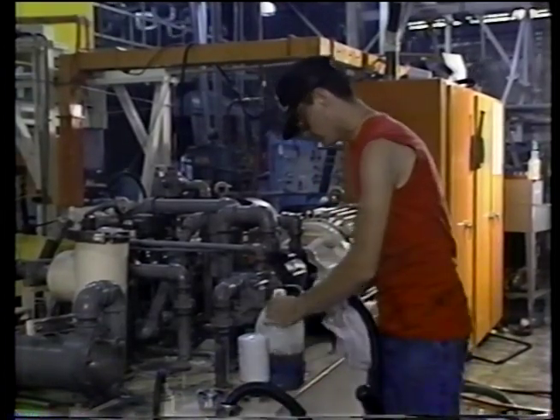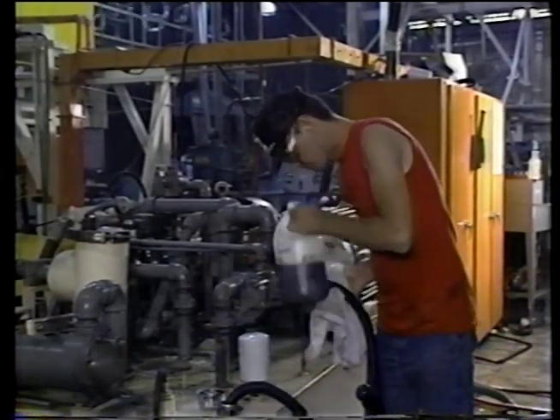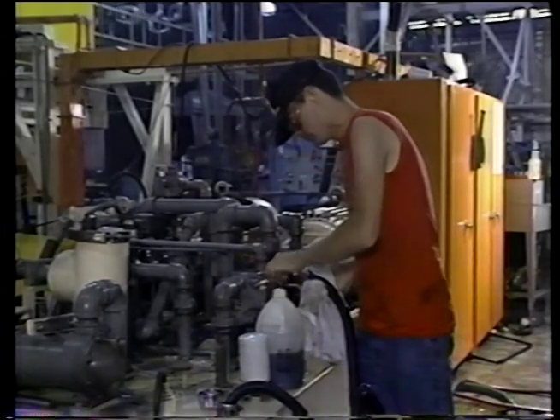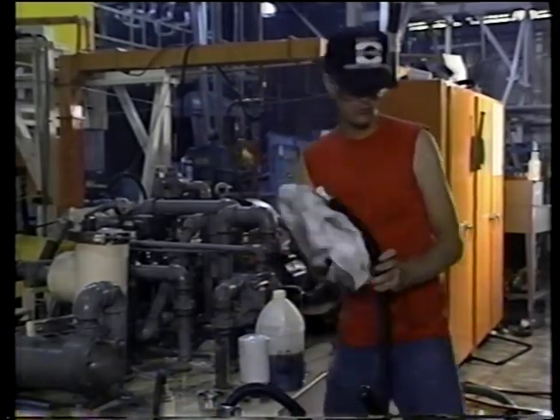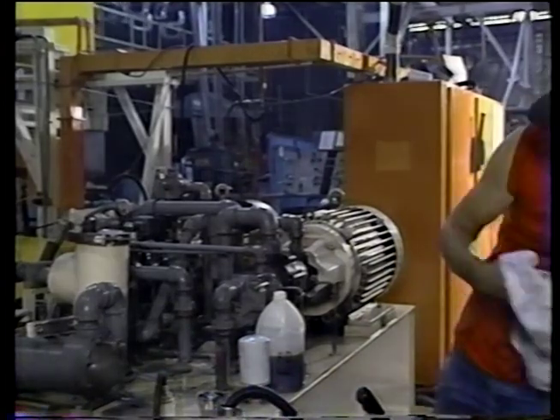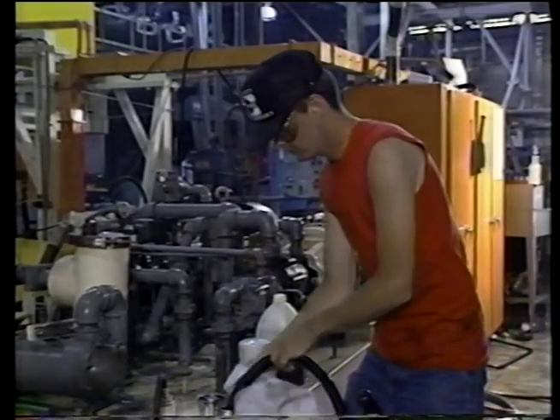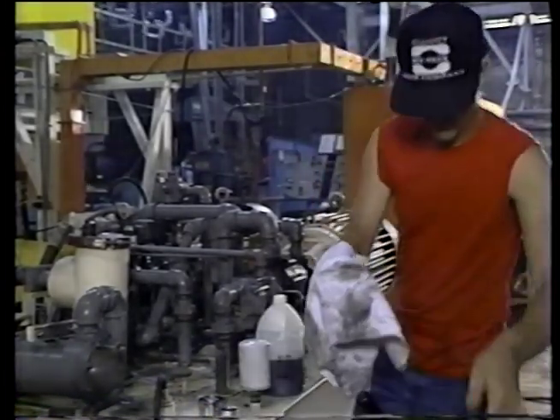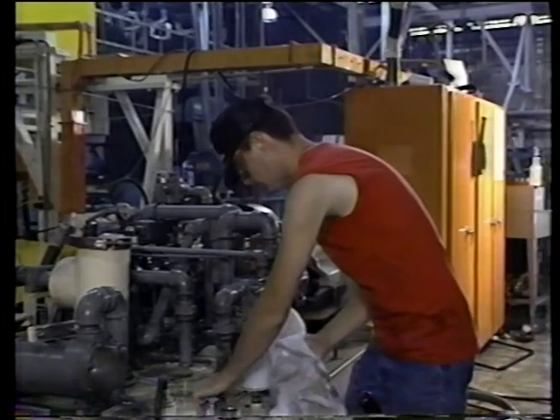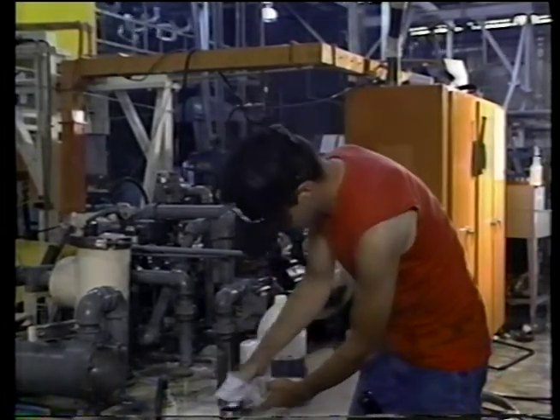If a fluid sample has either a burnt smell or feels too thin, and if a fluid analysis indicates that the fluid has been oxidized, you will have to drain and flush the system, clean the varnish deposits and sludge from components, and refill the system with fresh fluid.